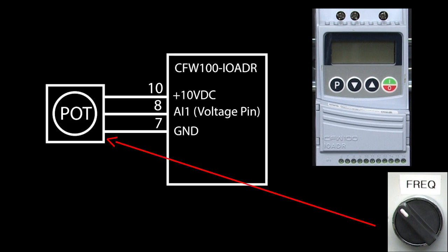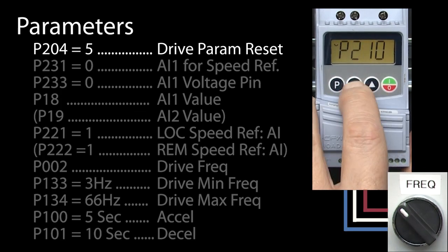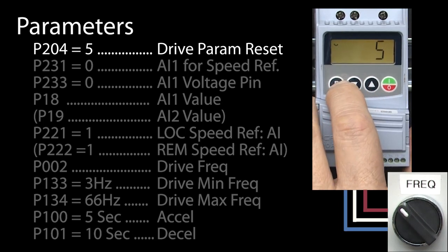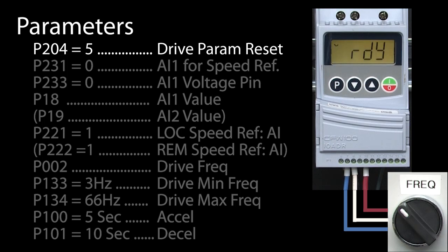I wired this potentiometer to analog input 1 like this. I'll apply power to the drive. Let's go to parameter 204 and set it to 5 to reset the drive parameters to factory default, just so we're all starting in the same place. Now, you wouldn't do that if you have an existing configuration you're trying to modify.